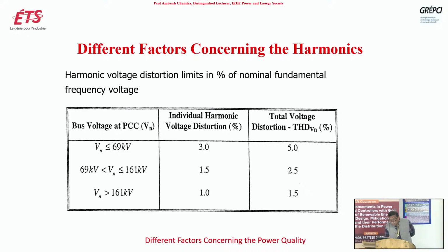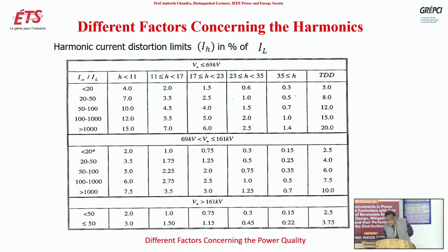Now, odd harmonic current distortion limit in percent. Here TDD is written, but the same limits are for THD also. So if the size of the distribution system increases, because this is the short circuit current divided by the load current, if short circuit level is increasing, it means perhaps the circuit breaker capacity is larger, perhaps they might be putting more, so that large system may have large current.